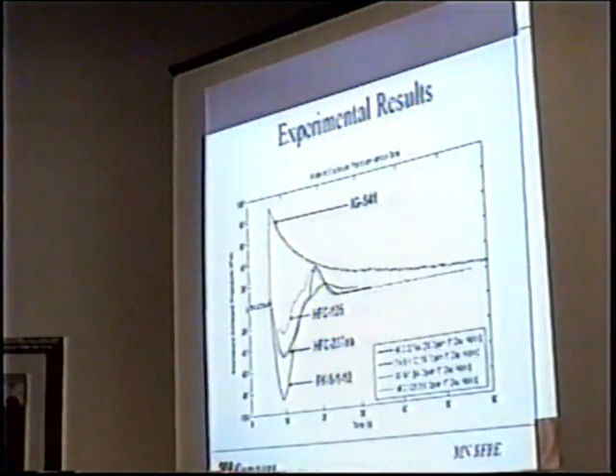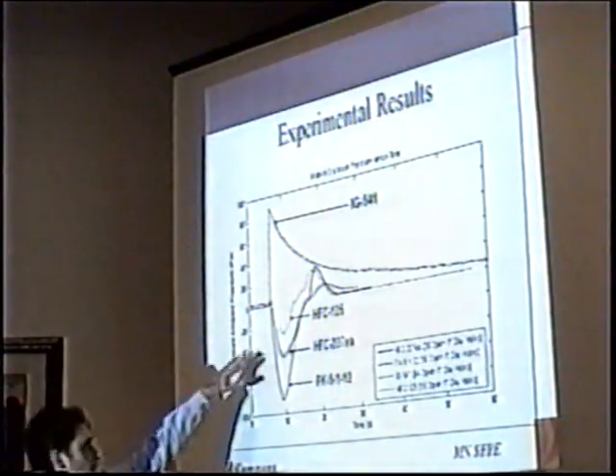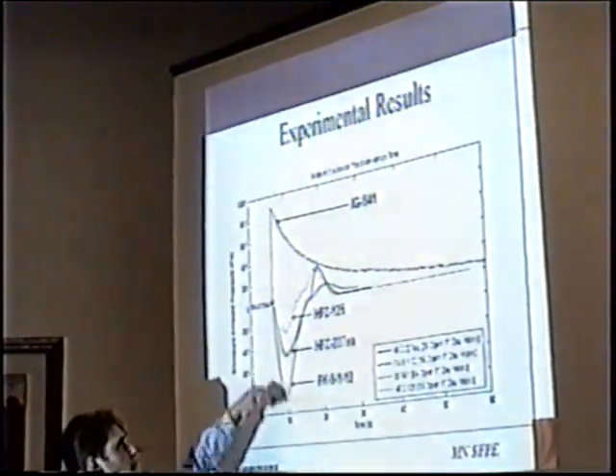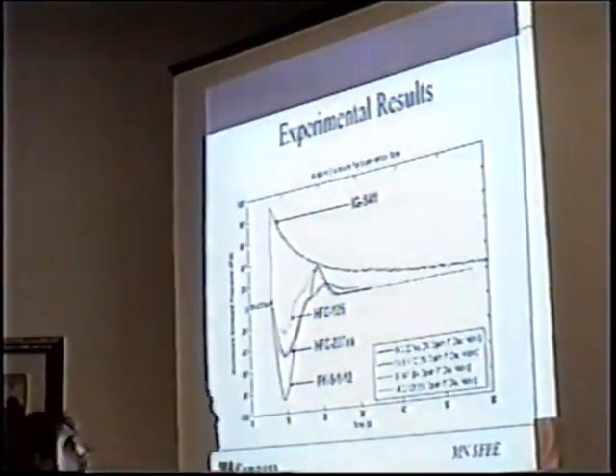This is the pressure spike that we see. Like I said, IG541 has got an issue with overpressurization. This is actually the loosest enclosure for IG541. We had to use a pressure relief vent to protect the enclosure for most of the tests. FK5112, a negative spike, the lowest, HFC-227ea, HFC 125.